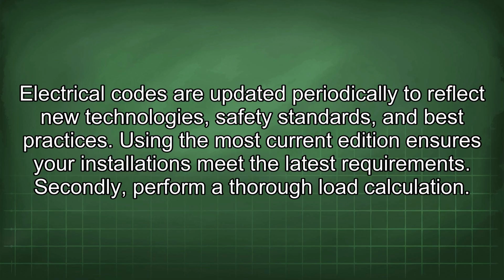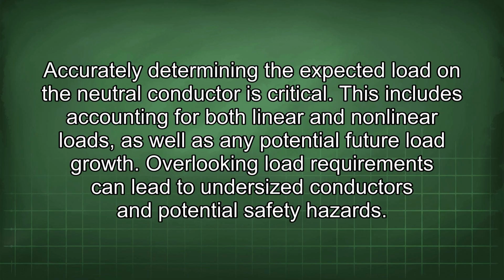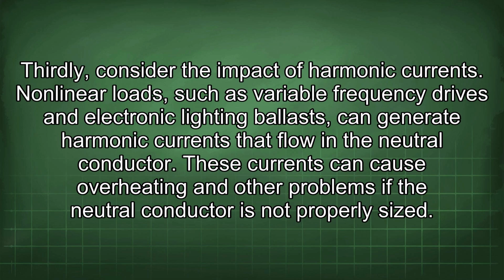Secondly, perform a thorough load calculation. Accurately determining the expected load in the neutral conductor is critical. This includes accounting for both linear and nonlinear loads, as well as any potential future load growth. Overlooking load requirements can lead to undersized conductors and potential safety hazards. Thirdly, consider the impact of harmonic currents.